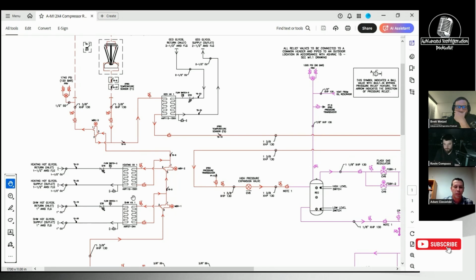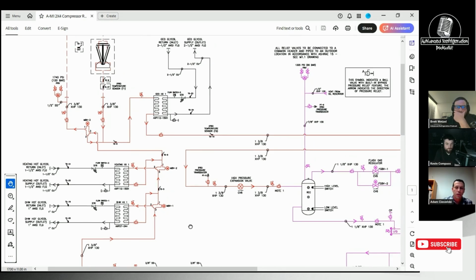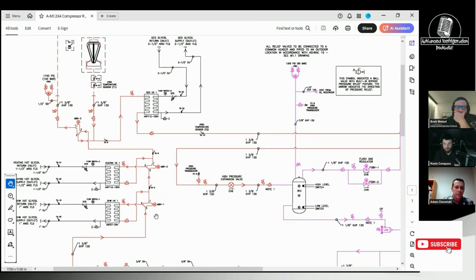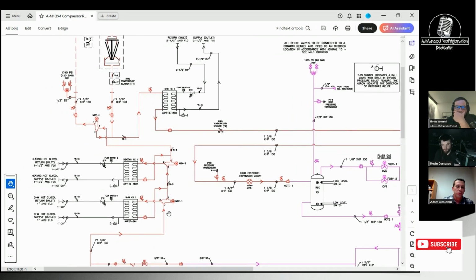The hot water load is pretty light. There's basically the public restroom is the only thing utilizing hot water. So it's a pretty light load, and the majority of efforts and focus really goes on to this heat exchanger, which produces the hot glycol for the wintertime conditions. Both of these heat exchangers utilize a Danfoss CTR valve, a modulating stepper valve. So we are controlling this based off of the supply temperature. When we get a call for heating from the building control, we'll enable these circuits, and then we'll modulate these stepper valves to produce the supply water temperature.